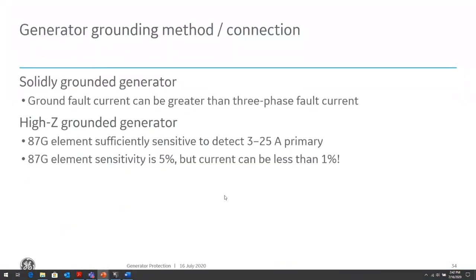So we talk about the more common types of fault in a generator, or in any protection system in general, which is the ground fault, right? And for a solidly grounded generator, not a problem. Ground fault current is pretty high. It's actually, for a solidly grounded generator, ground fault current can be greater than the three-phase fault current.